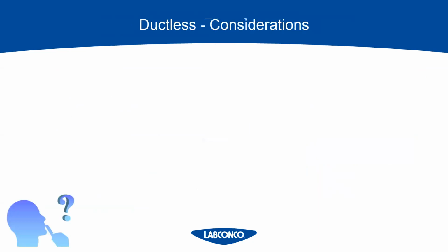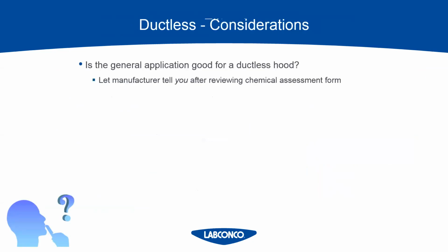So now we're going to go through different questions to consider when we're looking at both ducted and ductless hoods. And we'll find out by going through these which enclosure is going to be better for what application. So first, is the general application good for a ductless hood? Has the manufacturer reviewed your application and told you it's good to go? Any manufacturer who offers ductless fume hoods is going to be able to review the application and tell you if it's approved and how long they expect the filters to last. Like I said before, step one is always filling out the chemical assessment form. Second question is, how often do filters need to be replaced? Once again, the manufacturer will tell you this after you fill out your chemical assessment form.